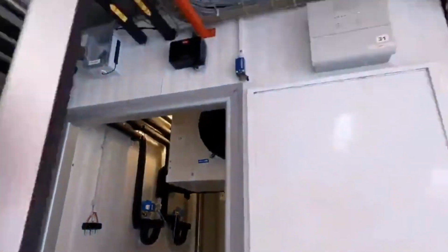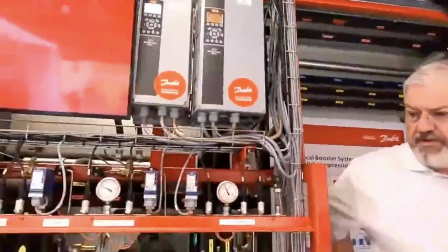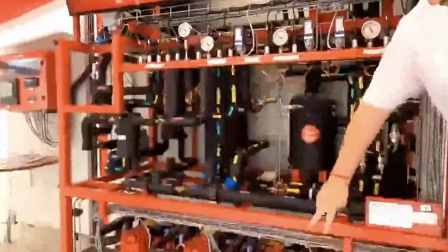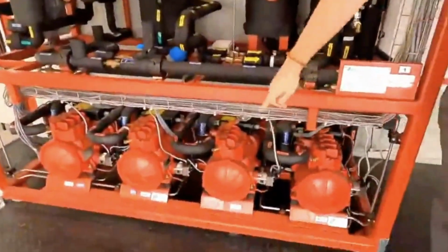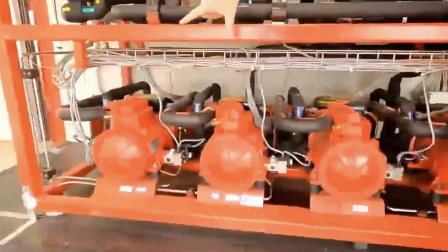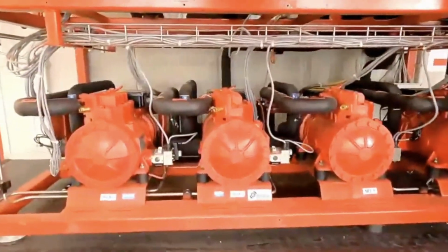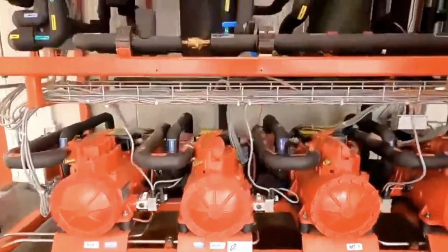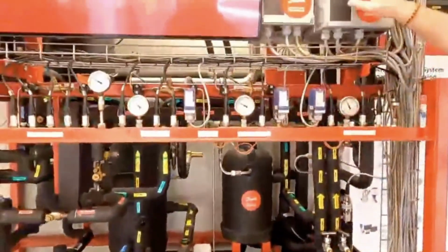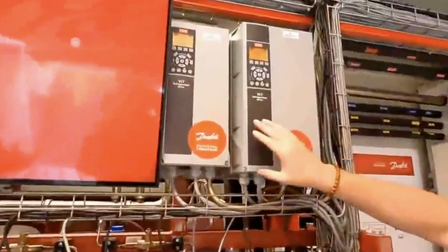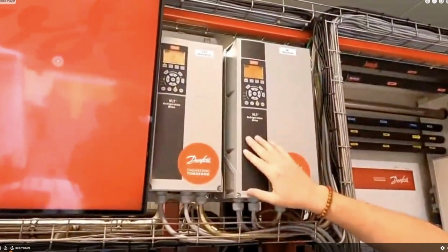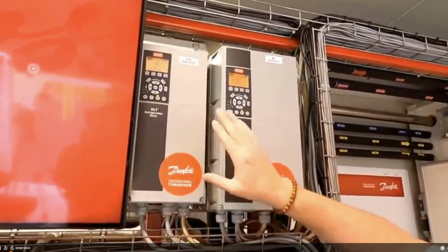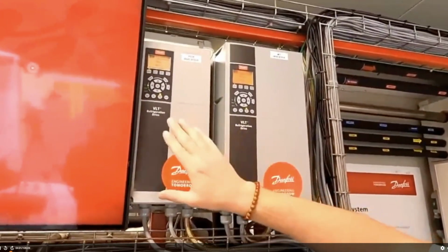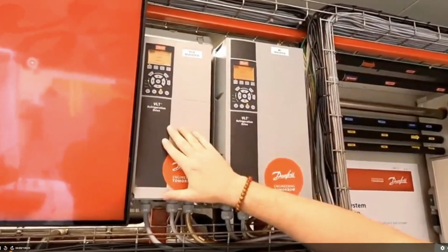Then our next close-up, if we go in front of the system here, just to kind of go over the system layout, these are our 2 medium temp compressors down here. Then we have 2 compressors on the left. Those are for parallel compression. One thing to note on transcritical systems, or really any CO2 system, you'll typically see a VFD on the lead compressor for each stage. So our medium temp inverter is here. Our parallel compression lead compressor inverter is here.